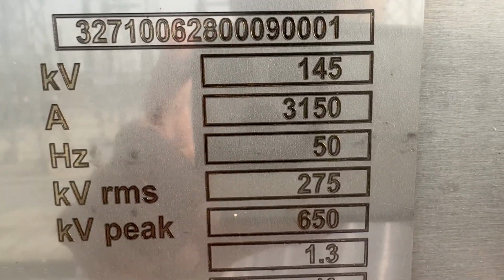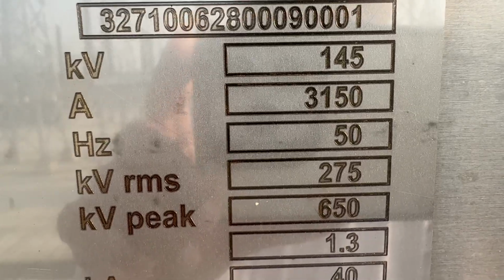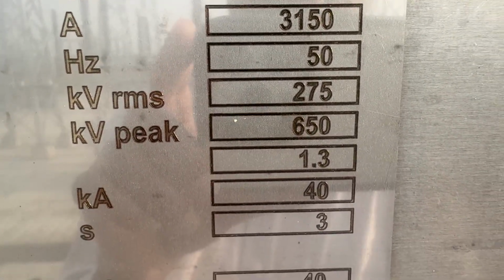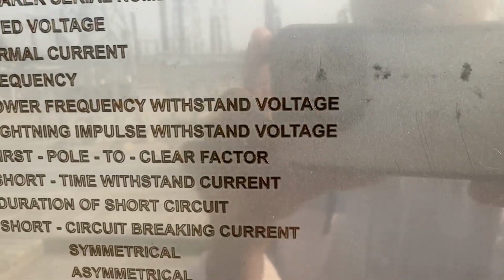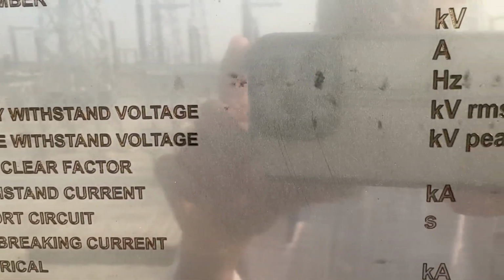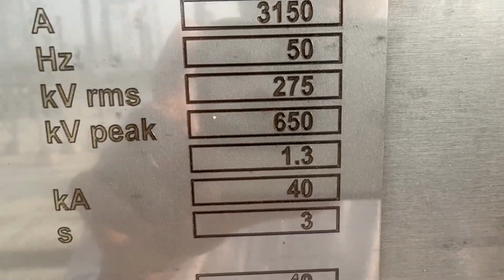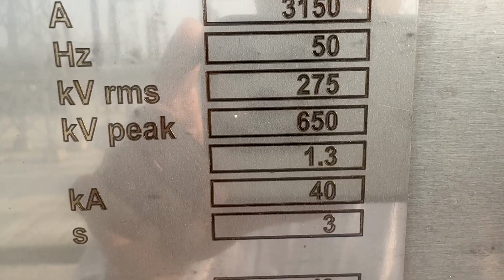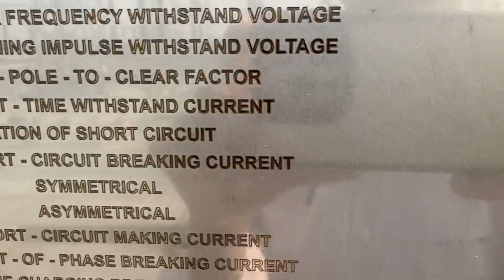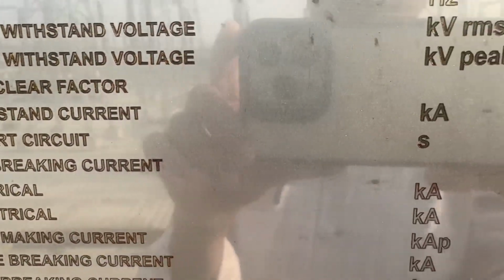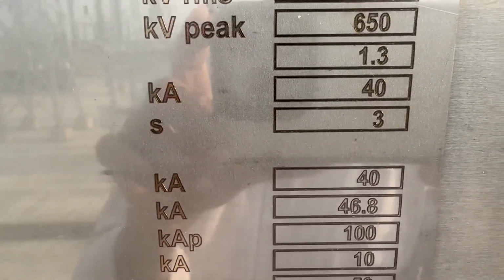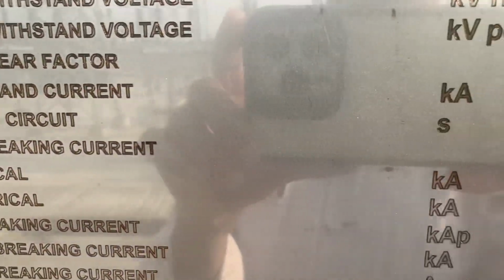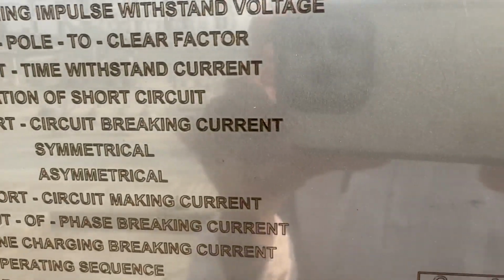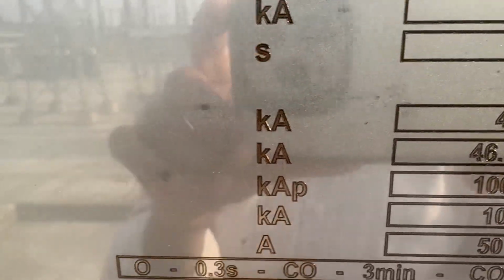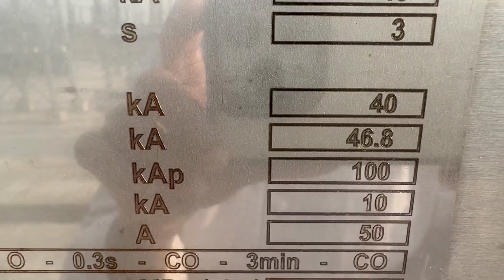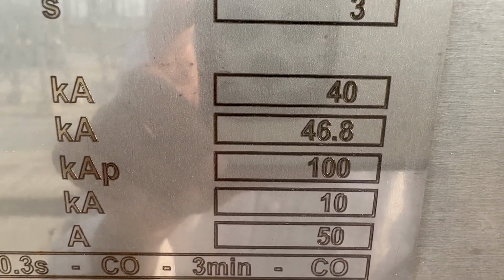Okay, let's see another rating. Rated ampere is 3150 ampere. Frequency 50 Hz. Power frequency withstand voltage is 275 kV, and lightning impulse withstand voltage is 650 kV. First pole to clear factor is 1.3. Short time withstand current is 40 kiloampere. Short circuit breaking current, symmetrical, is 40 kiloampere, and asymmetrical is 46.8 kiloampere.